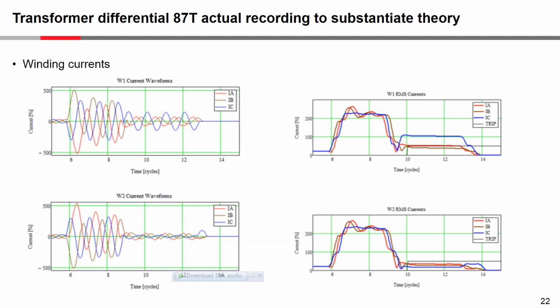And what happened is, initially there was an external three-phase fault. Okay, so that is not too important for us right now, but there was a three-phase external fault. And when that three-phase external fault cleared, you can see where the transition is. The three-phase fault, when it cleared, actually became an internal C-phase fault. And we're going to be looking at the current values from winding 1 and winding 2 during the time of the internal C-phase fault, because this is the single-phase fault, and we're hoping to see similar information from a measured event to what my theoretical calculation showed.